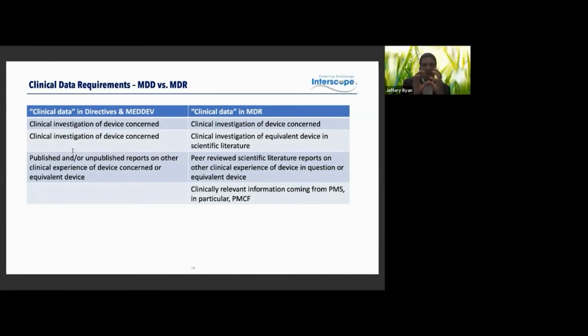You've got, again, the clinical investigation in Europe on MDR is of the device concerned. So you've got to make sure that you're doing a clinical study specifically on your device. Now, this means I can't pull a retrospective series together on something that's similar and say that's the data I'm going to use in order to submit. We really got to do it. The game has changed. Peer-reviewed scientific reports. That's very, very different here. Making sure you've not only done the data, acquired the data, done the research, but you've actually gotten published. That's a very, very big difference than we had before.